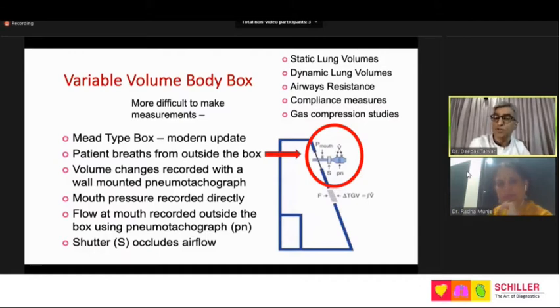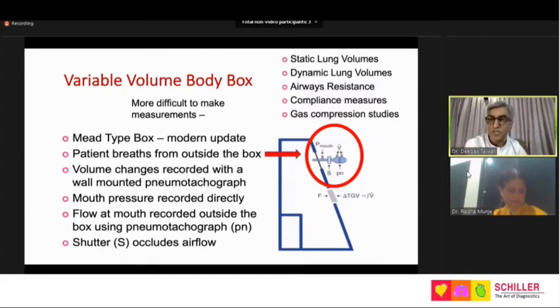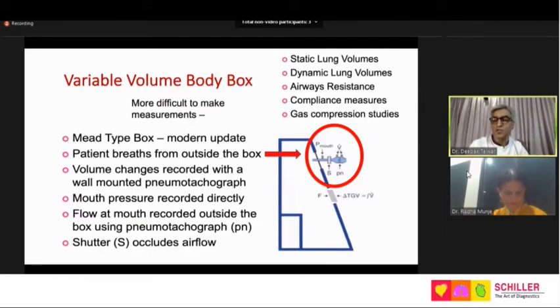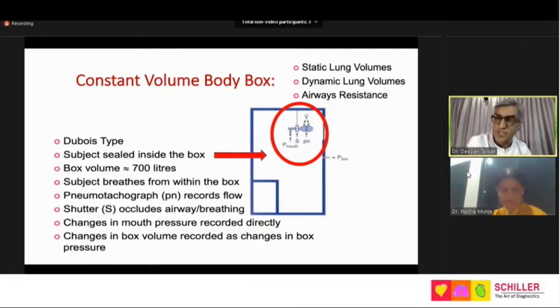The variable-volume box can also do compliance and gas compression studies. For compliance you need to pass an esophageal catheter with an esophageal balloon to record esophageal pressure. These earlier body boxes were used for compliance research. What is more easily available now is the constant-volume body box, which provides lung volumes, dynamic lung volumes via spirometry, and airway resistance and conductance — all in one.